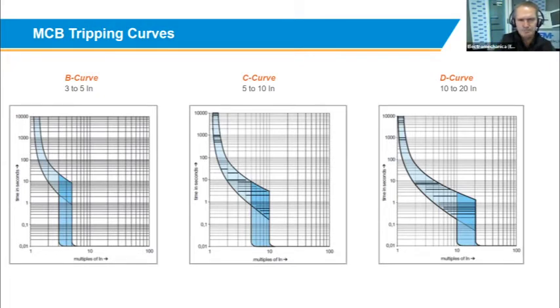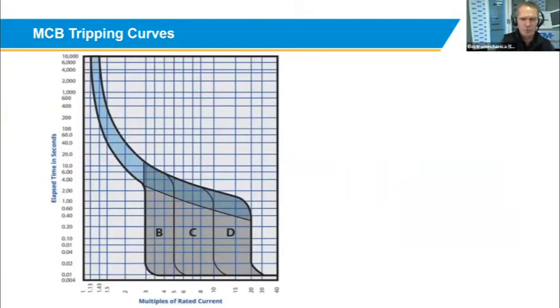So B curve is normally your fast tripping curve to protect sensitive equipment. C is the standard norm that's normally used in residential and commercial applications. And then D curve is seen as a slow tripping curve, which allows a little bit more inrush, especially for motor applications. So you'll see here all the curves combined, the B, C, and D curves. And what do they mean? You'll see that on the thermal part of the curve, they are all actually the same. It only comes in with inrush and short circuit applications, where there's a difference.